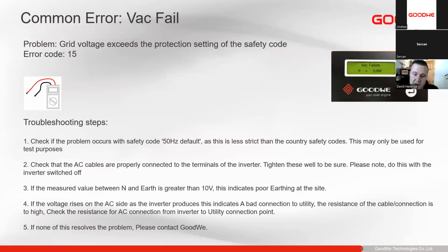Next, we also need to measure the voltage between neutral and earth, and make sure that it is less than 10 volts. If it is higher, it could indicate poor earthing. Like I say, sometimes maybe the earth is not tight enough somewhere and it's not making correct contact, with oxidation on the cables or anything like that. And if it still doesn't resolve it, then you can contact our teams for support.